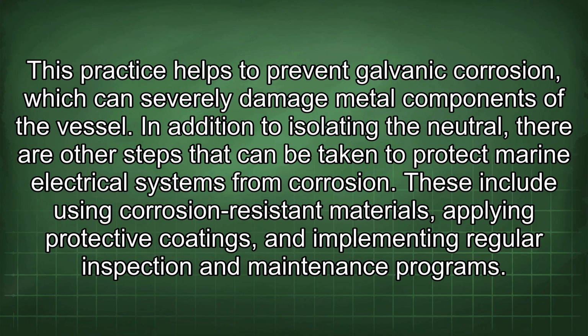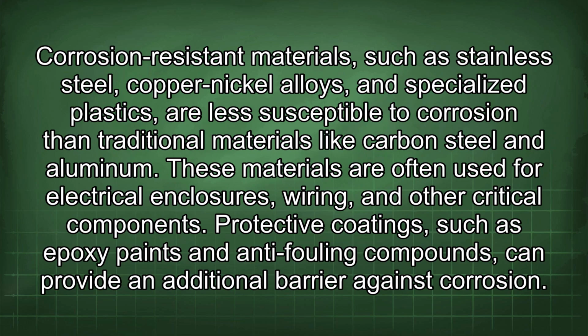In addition to isolating the neutral, there are other steps that can be taken to protect marine electrical systems from corrosion. These include using corrosion-resistant materials, applying protective coatings, and implementing regular inspection and maintenance programs. Corrosion-resistant materials such as stainless steel, copper, nickel alloys, and specialized plastics are less susceptible to corrosion than traditional materials like carbon steel and aluminum. These materials are often used for electrical enclosures, wiring, and other critical components.